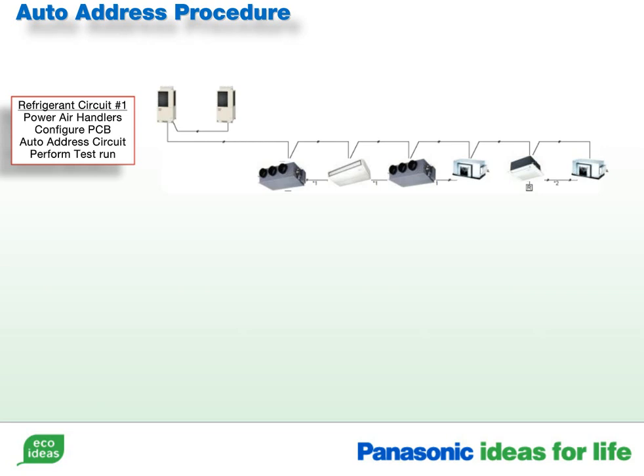When commissioning multiple refrigerant circuits, there is a certain order in which it should be performed. Let's start with refrigerant circuit number 1. Apply power to the condensers for a minimum of 5 hours. Apply power to all of the indoor units. Configure the main PCB settings. Auto-address the refrigerant circuit and perform a test run of the refrigerant circuit.